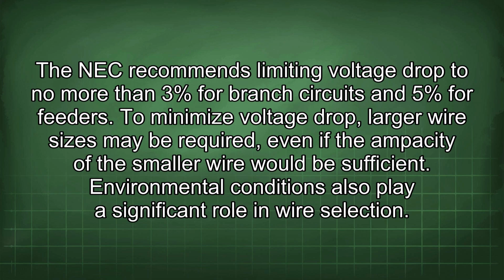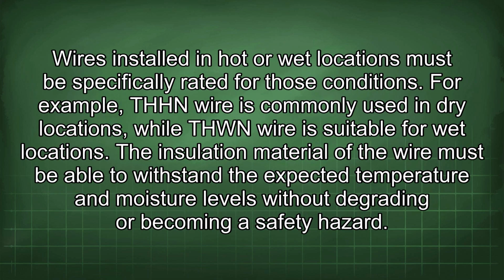Environmental conditions also play a significant role in wire selection. Wires installed in hot or wet locations must be specifically rated for those conditions. For example, THHN wire is commonly used in dry locations, while THWN wire is suitable for wet locations. The insulation material of the wire must be able to withstand the expected temperature and moisture levels without degrading or becoming a safety hazard.